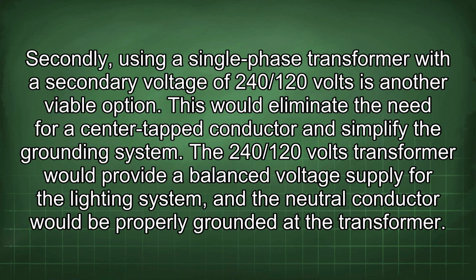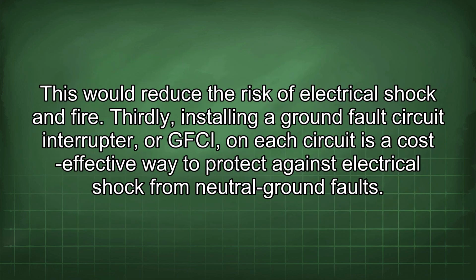Secondly, using a single-phase transformer with a secondary voltage of 240/120 volts is another viable option. This would eliminate the need for a center-tapped conductor and simplify the grounding system. The 240/120 volts transformer would provide a balanced voltage supply for the lighting system, and the neutral conductor would be properly grounded at the transformer. This would reduce the risk of electrical shock and fire.